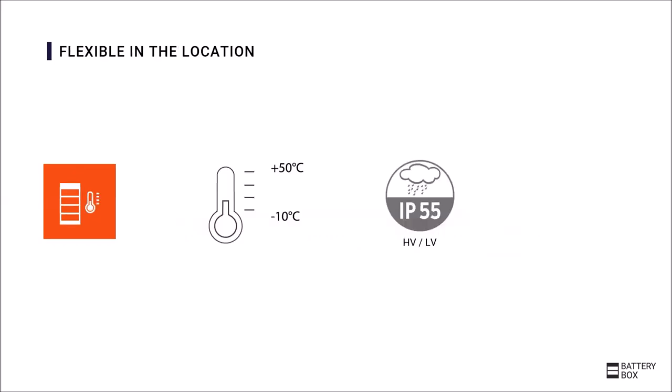The Battery-Box is also flexible in the installation side. The temperature range is minus 10 degrees to plus 50 degrees, which is a very wide and flexible range for lithium batteries. The Premium HVS, HVM and LVS also have a protection class of IP55.